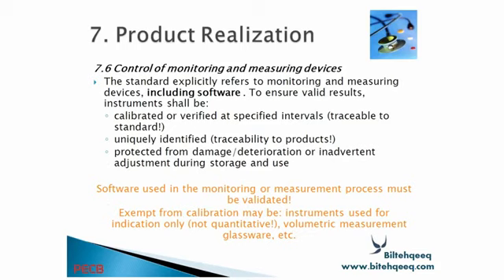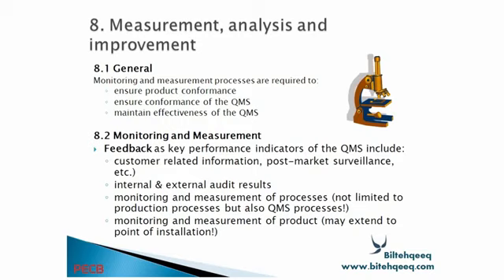Control of monitoring and measuring devices is the same as in ISO 9000. The standard explicitly refers to monitoring and measuring devices including software to ensure valid results. Instruments shall be calibrated or verified at specified intervals based on standards, uniquely identified with traceability, protected from damage, deterioration or inadvertent adjustment during storage and use. Software used in monitoring or measurement processes must be validated. Every instrument used for measurement must be calibrated. Monitoring and measurement processes are required to ensure product conformance and conformance of the quality management system.